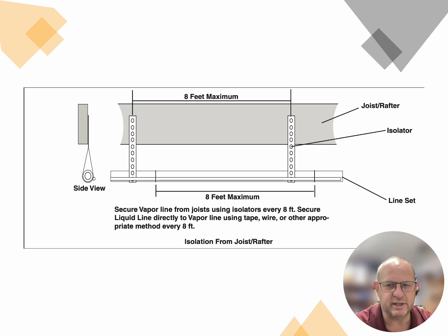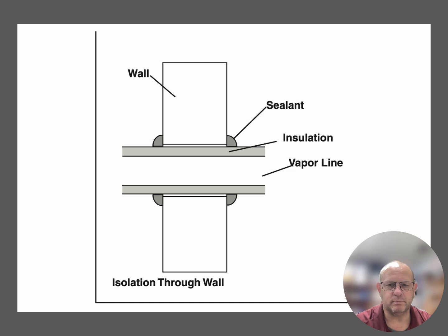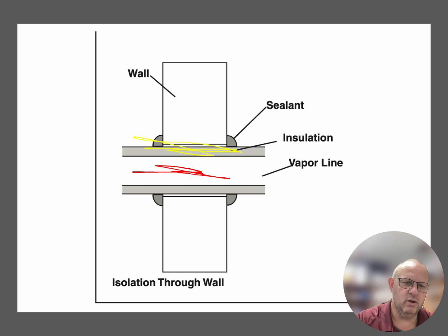And when we look at actually going through a wall, I'm going to sleeve this line. So here's my line set. I want to take that line set and sleeve it with some sort of plastic pipe and run it through that plastic pipe, so I'm not touching any wood or any material that can rot away, just in case the vapor line does leak a little bit of vapor through it into that environment.